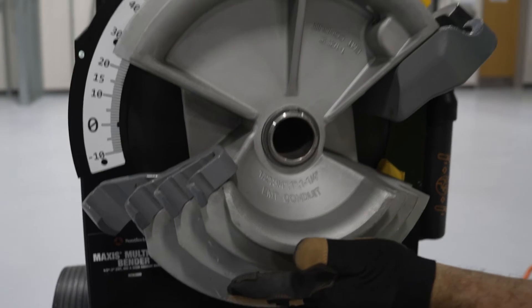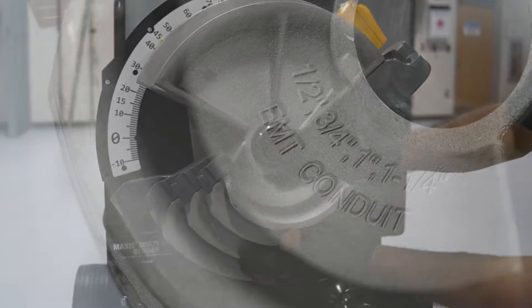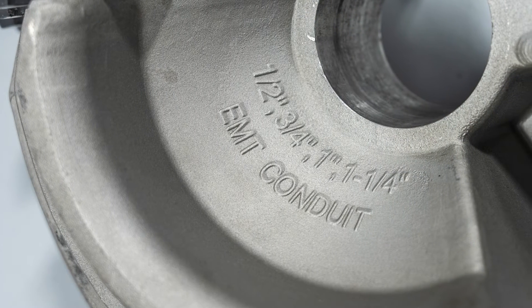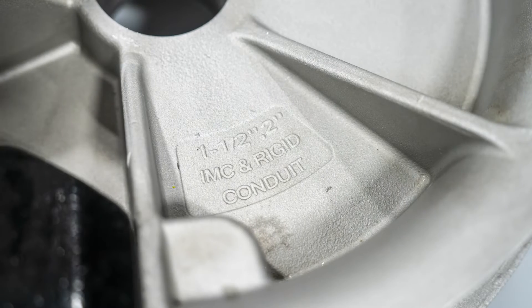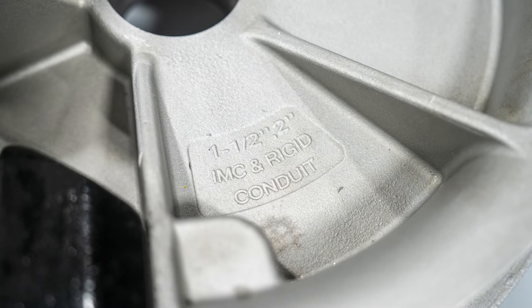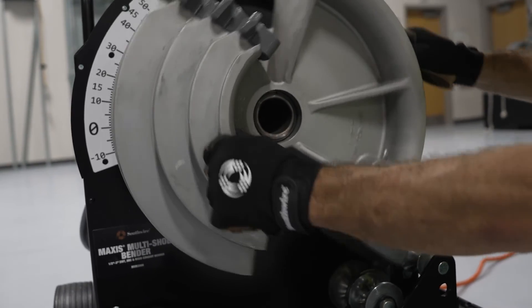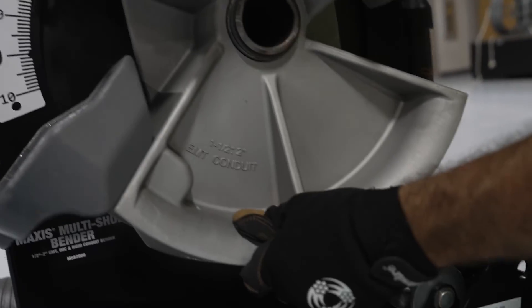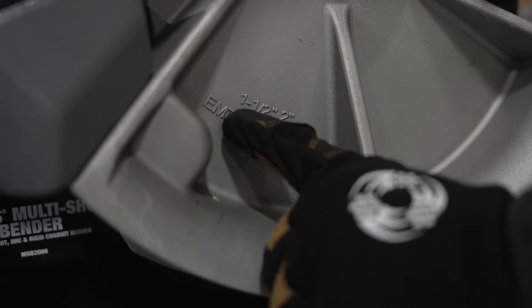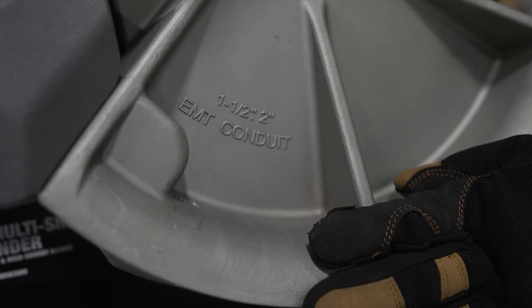Notice that the bending shoe is separated into two halves. One half of the shoe is used for bending half-inch, three-quarter, one, and one and a quarter inch conduit. The other half of the shoe is used for bending inch and a half and two-inch conduit. You can also see markings that are cast into the center of the shoe indicating the conduit size for each half. Today we're going to be bending two-inch EMT conduit, so I'll be using this half of the bending shoe.